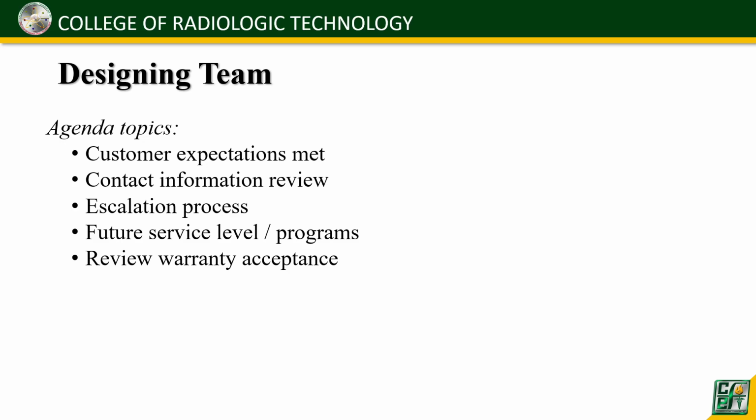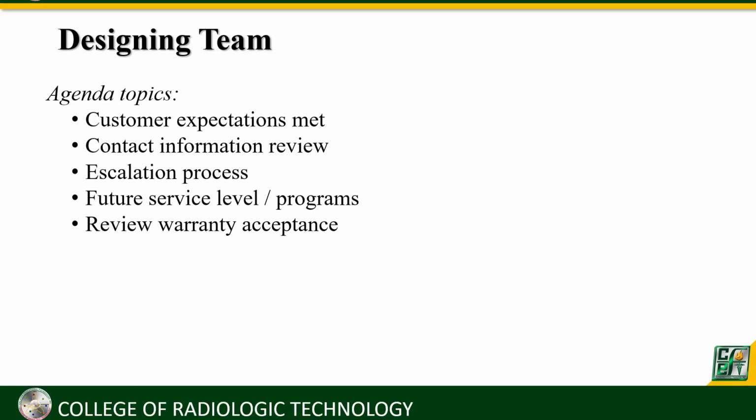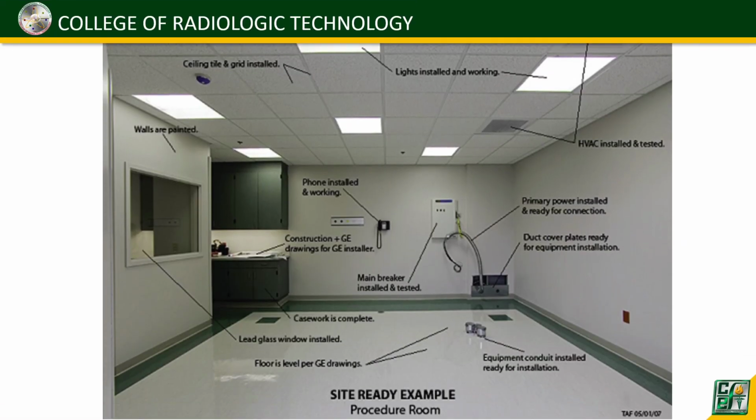Okay? Then, the acceptance. So, after conducting an acceptance testing, kung pasado siya doon sa binigay na specs, okay, at sa mga test, so, ayan, magkakaroon ng acceptance ng machine. Okay. So usually yung pumipirma ay either the Director of Radiology or the Chief Tech.